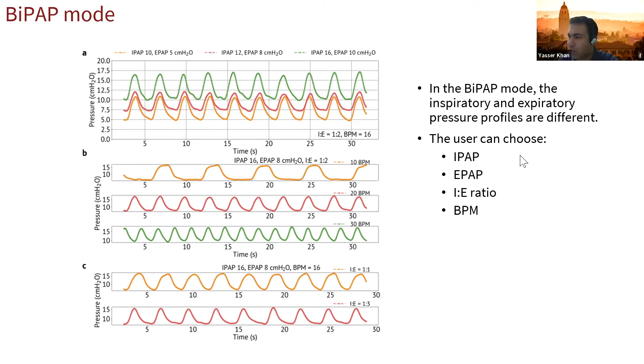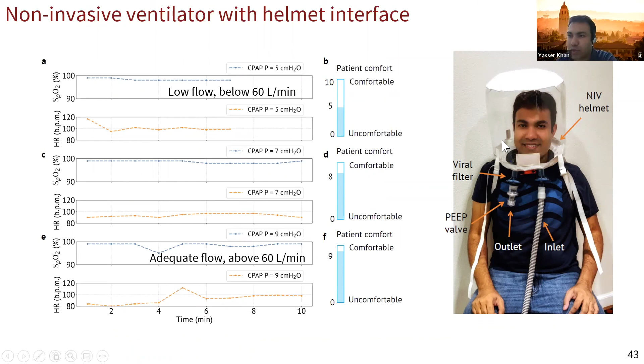And as I mentioned, the flow is really important because if you don't have enough flow, your CO2 will be trapped and you will start rebreathing the CO2. And what we saw is, if we maintain an adequate flow over 60 liters per minute, it's much more comfortable wearing the helmet. Here I'm showing the unit in action.